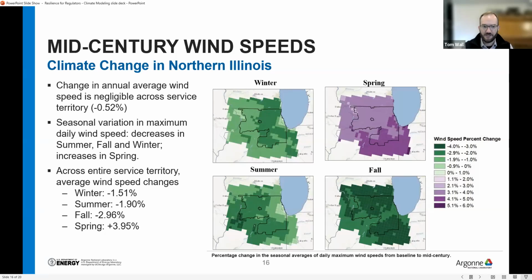Across northern Illinois, average annual wind speed doesn't change much—a half percent change is within normal interannual variability. What was striking is that winter, summer, and fall all show a decrease in wind speeds, but spring gets windier, particularly in the southern portion of the region. Some of the greatest decreases in wind speed are in fall, in the northern and southern portions of the region. This is interesting for ComEd in thinking about changes to renewable energy, but also has implications for general windiness, which helps cool conductors and equipment. If wind is going down, particularly in summer when it's hottest, that may affect equipment cooling.